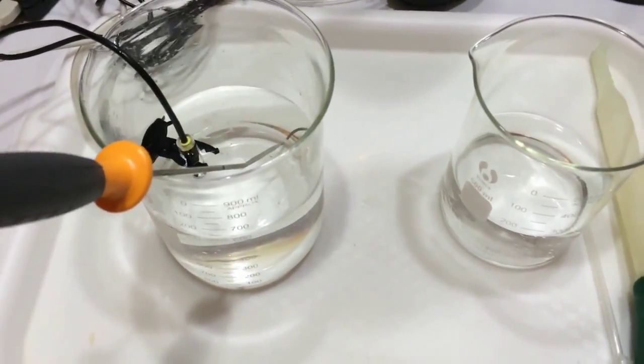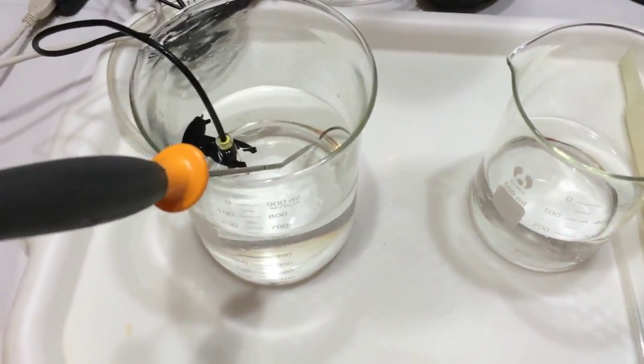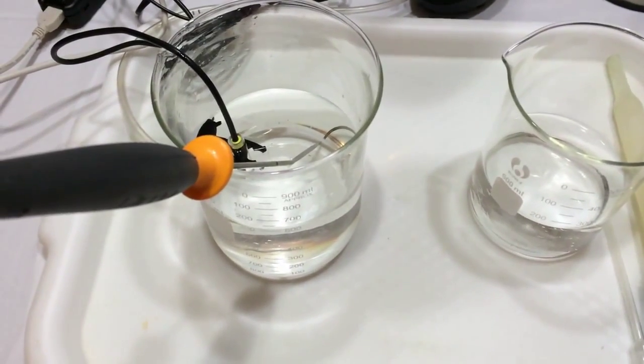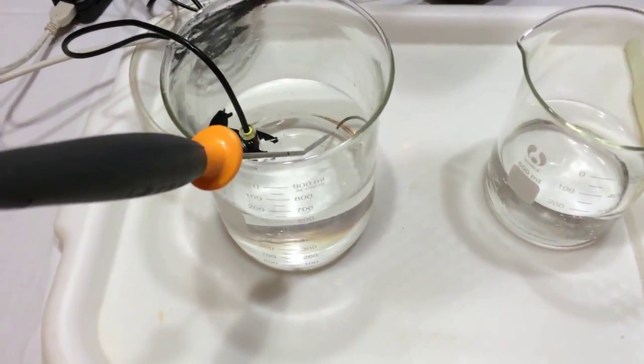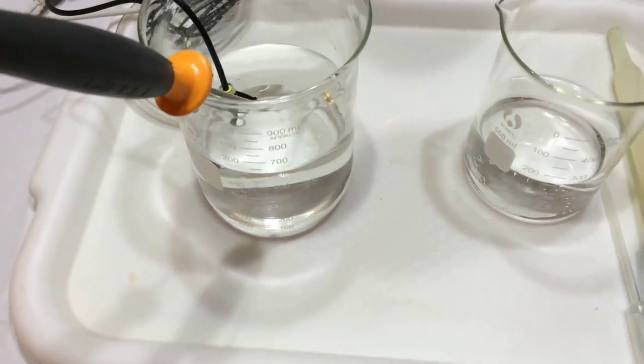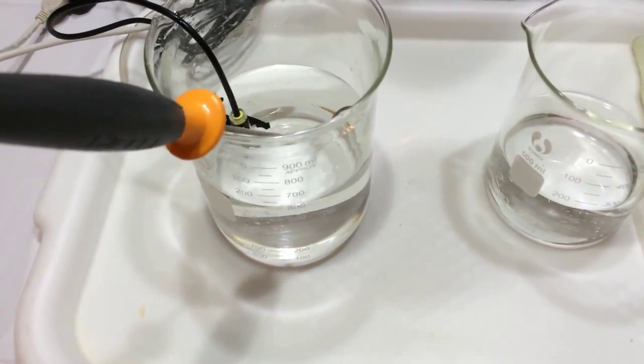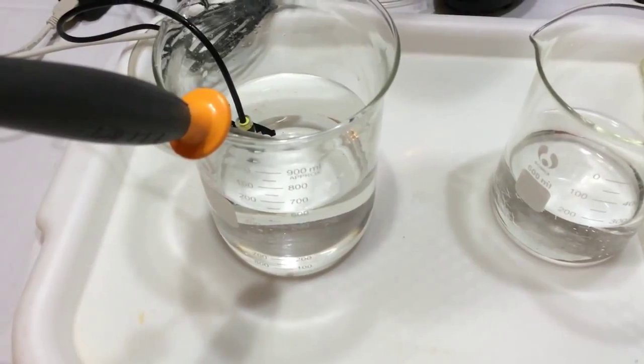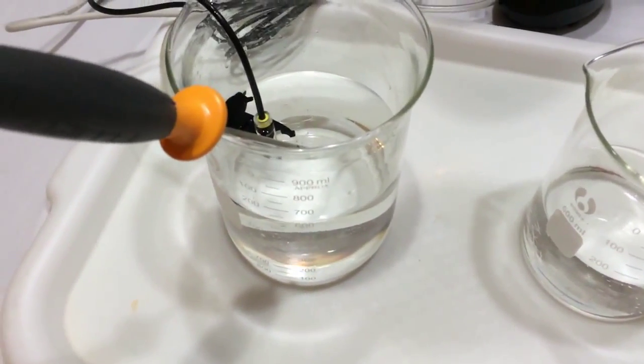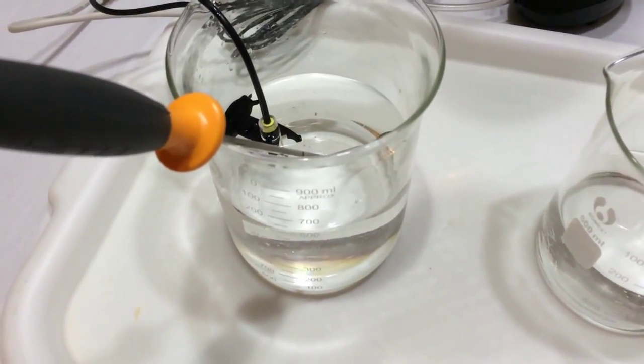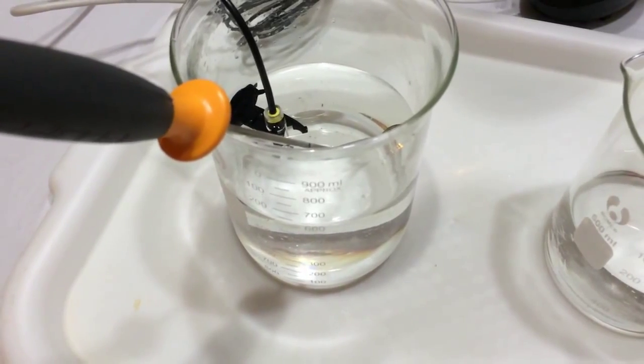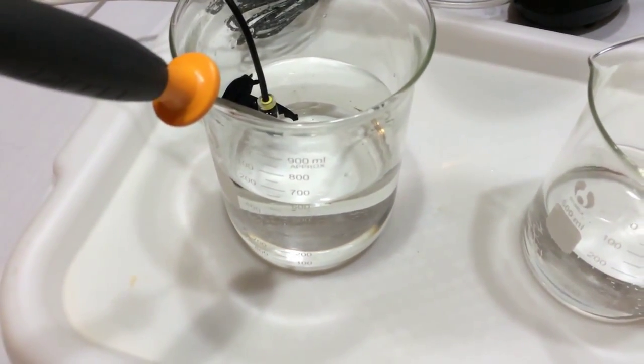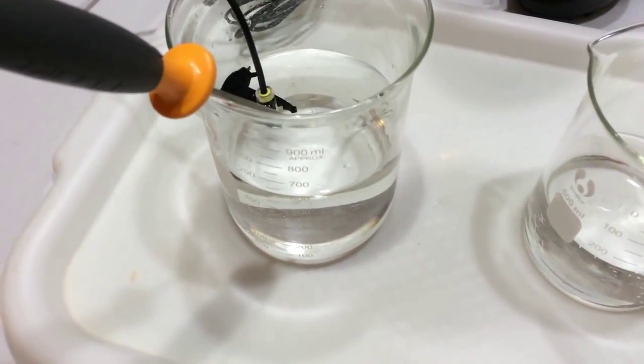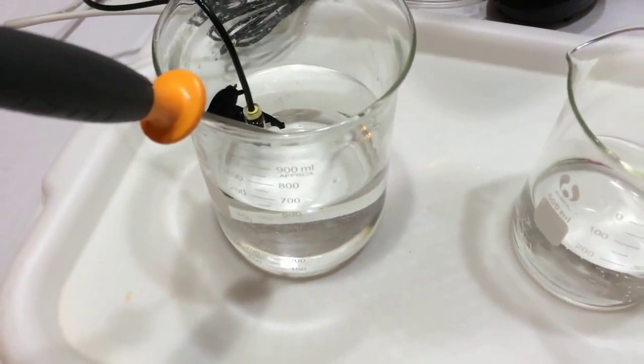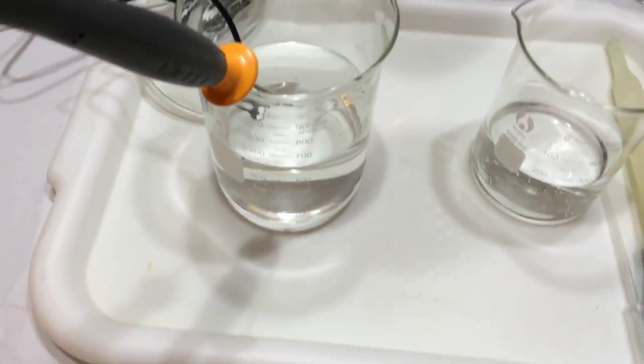Aquatronica says that the probe is pretty much factory calibrated and is pretty accurate out of the box, so you don't necessarily need to calibrate it. But if you don't feel comfortable and you want to calibrate it, and you don't have something like this, I suggest you buy a low scale thermometer. That's basically one that'll go between a region of like 20 degrees Celsius to 27 degrees Celsius. They make thermometers like that, and they're big. They're long, so they give you a very accurate reading. Those are probably one of the most accurate things, short of using one of these digital units, or probably could even be more accurate. So let's go look at what the actual reading is on the Aquatronica.